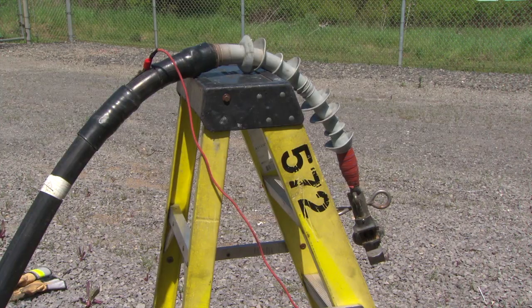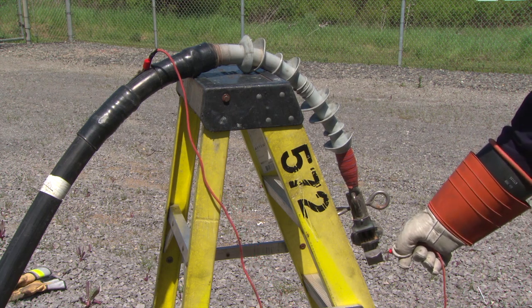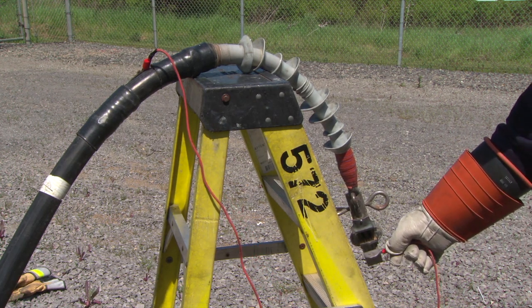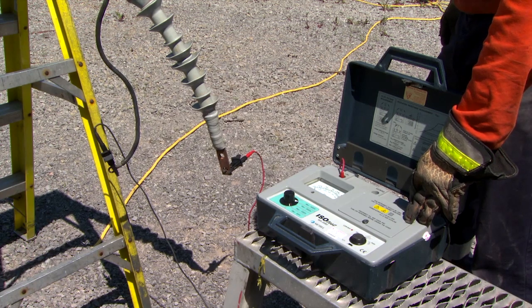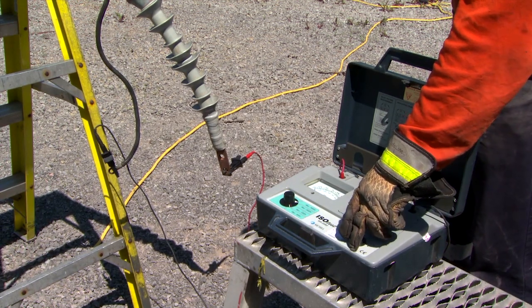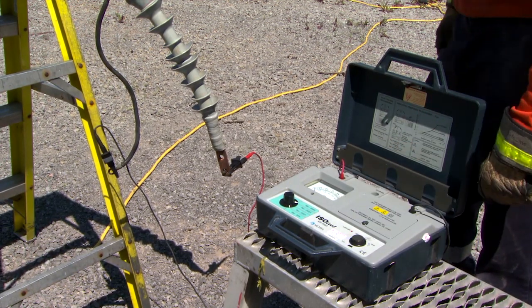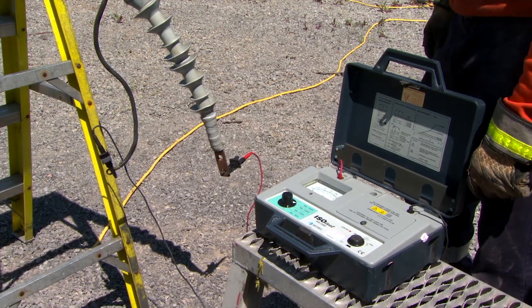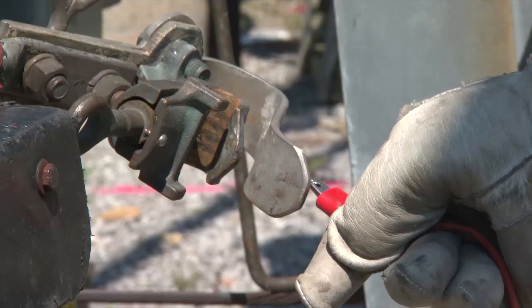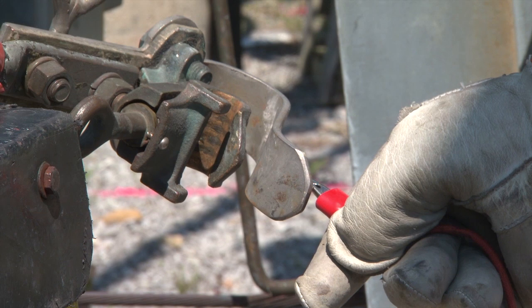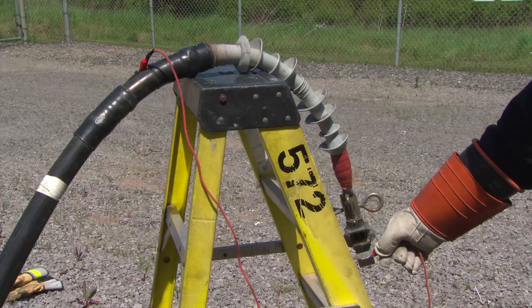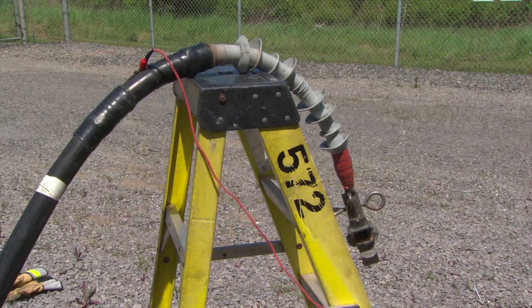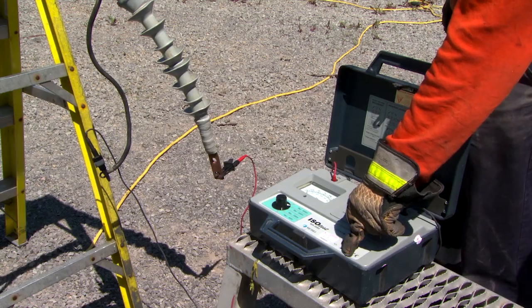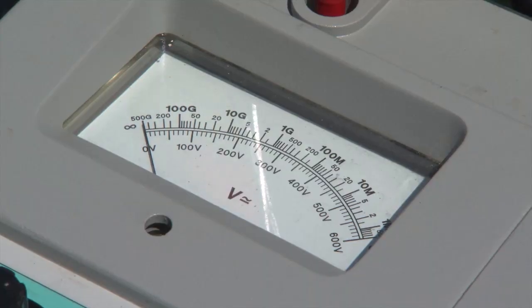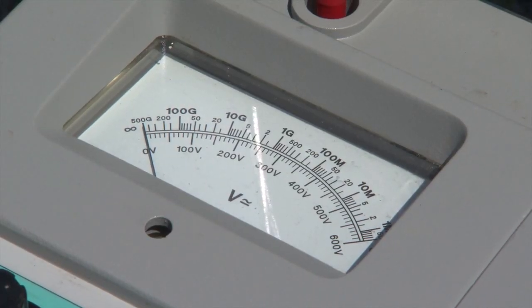Using rubber gloves, place a jumper lead between the concentric neutral and the cable conductor. Set the Megger test voltage to 1000 volts and connect one test lead to the conductor and the other to the concentric neutral. Test for continuity. Using rubber gloves, remove the jumper. Megger test the cable insulation to the concentric neutral at 1000 volts for 1 minute. Record test results on the MUS record.